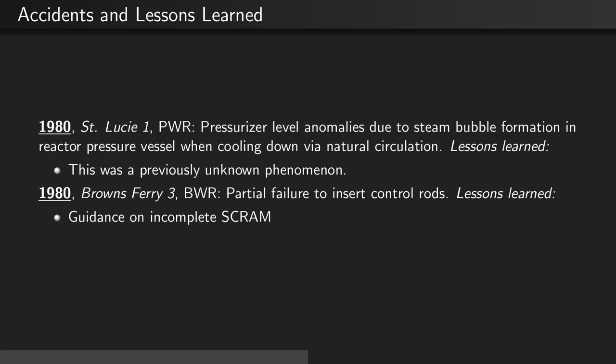Also in 1980, at Brown's Ferry 3, a BWR, there was a partial failure to insert control rods. The lesson learned was that there needed to be further guidance on incomplete scrams.